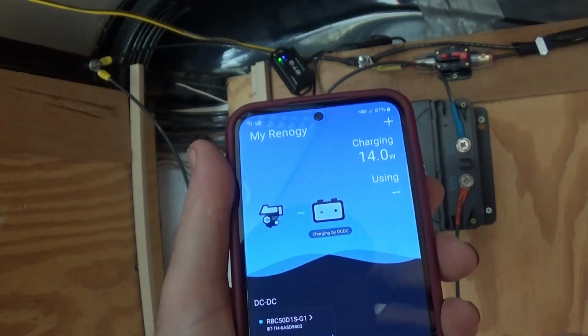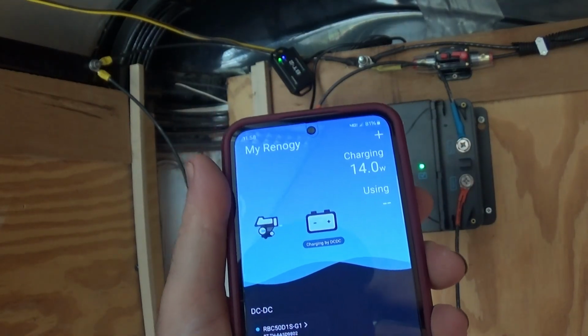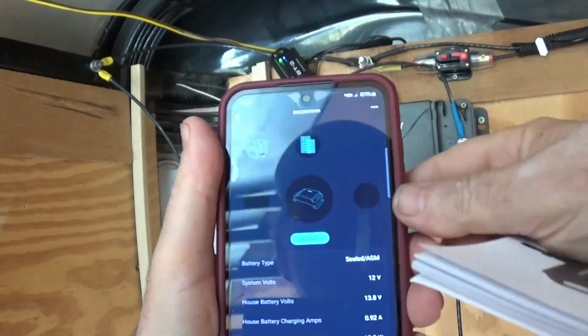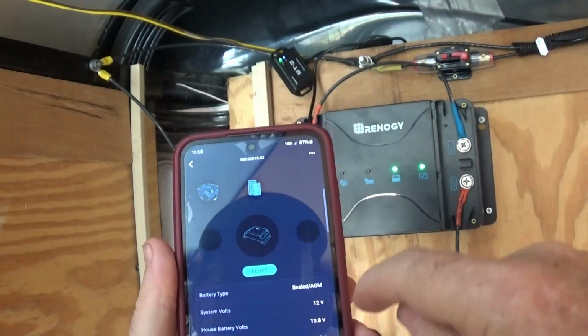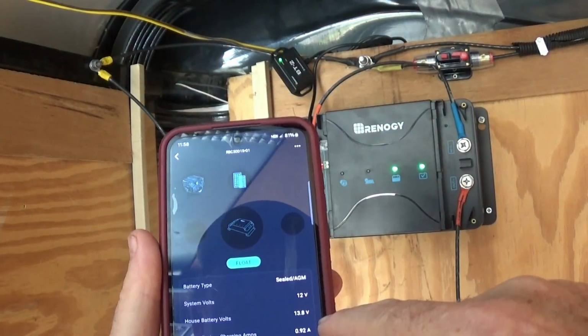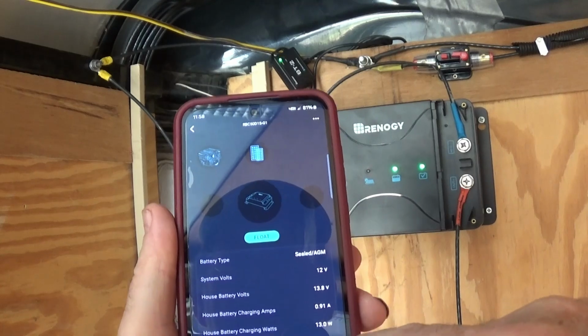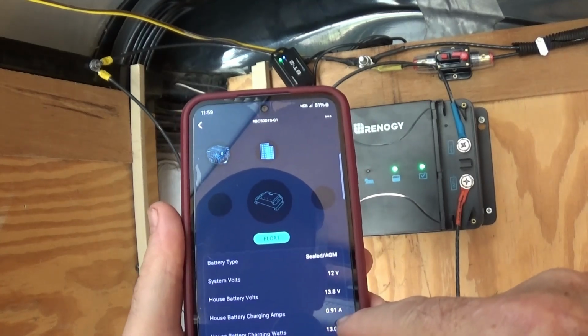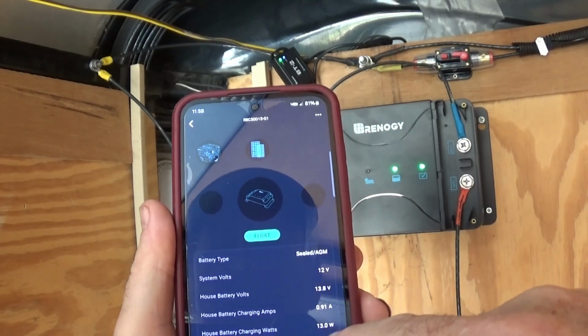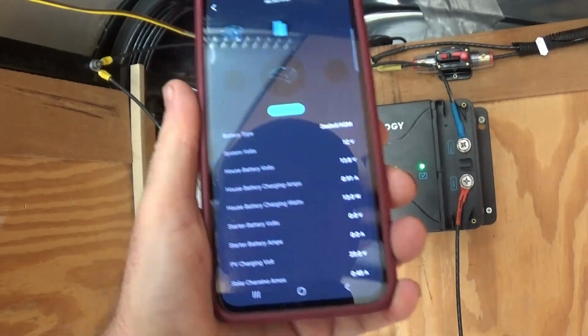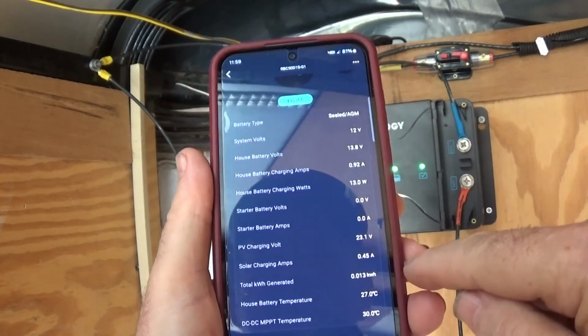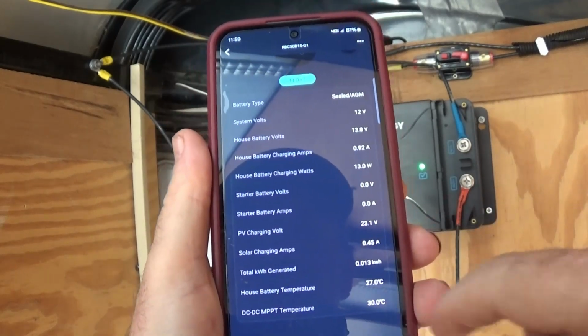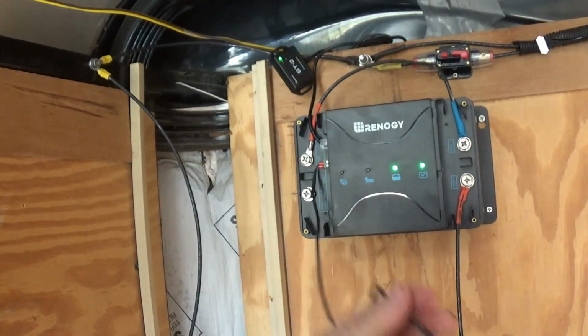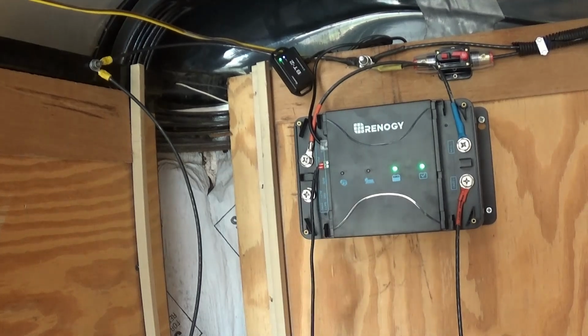But charging says 14 watts, less than an amp, because everything's floating. So you tap on that and it says it's in float. Battery type sealed AGM, system volts 12, house battery volts 13.8, you can read it, 0.9 amps charging. So there's some of the data it gives you, and it says the temperature too, that's from this sensor here, it's just hanging there right now.